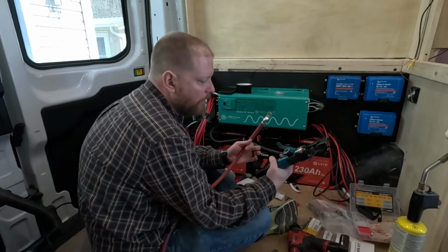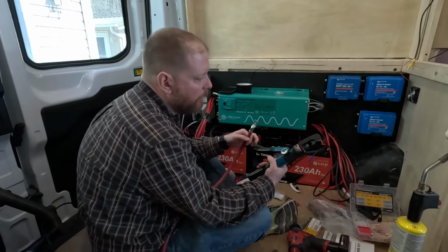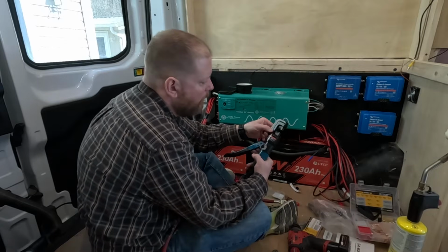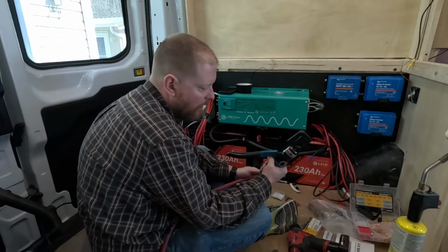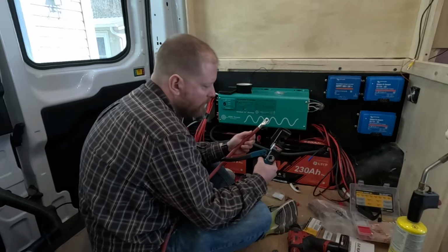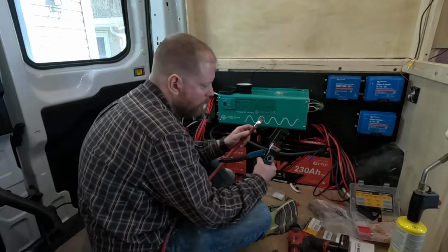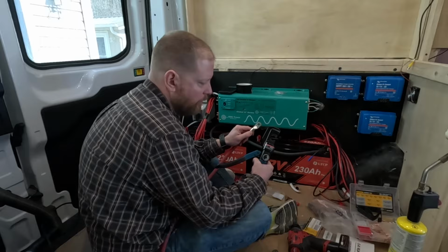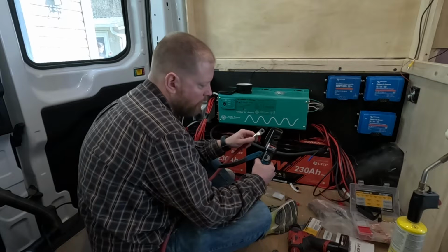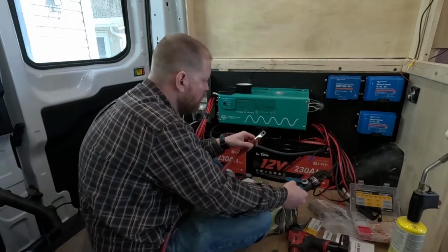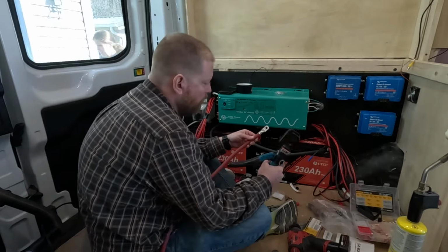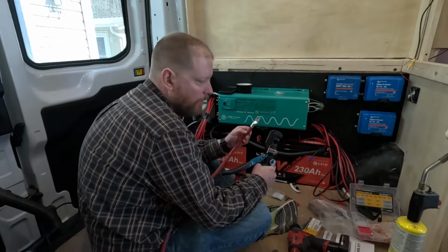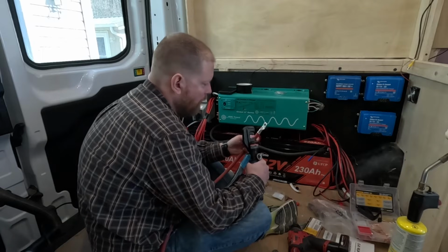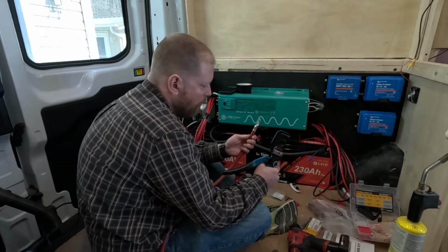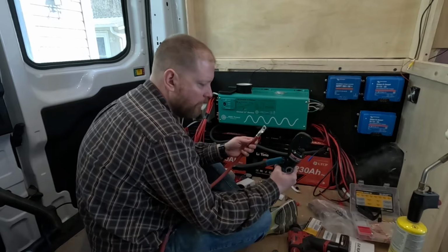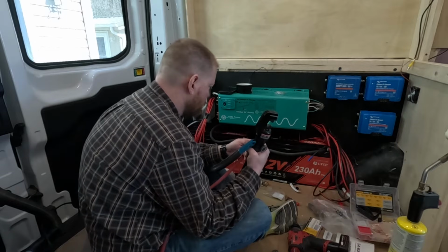It's not that expensive, you just pump this cylinder here and put different size dies in it. I'm using the 1/0 die on the 2/0 cable just because I want a little bit tighter of a crimp. These are pretty important, that they're crimped good, so I'm just using one size smaller than what it says to use. You could also crimp and solder, but you never want to just solder these. You have to have a mechanical crimp on these cables, and you need something really strong like this. So I'll put a link in the description for this one.